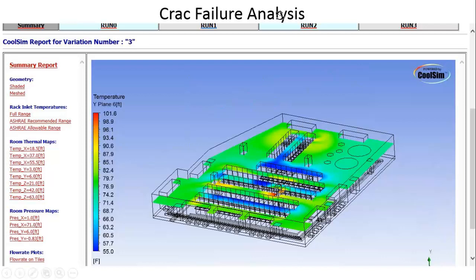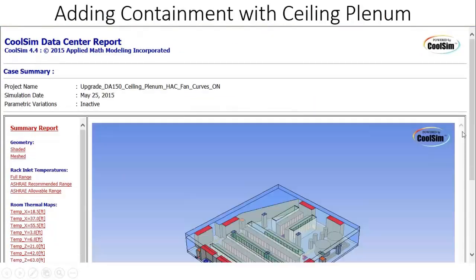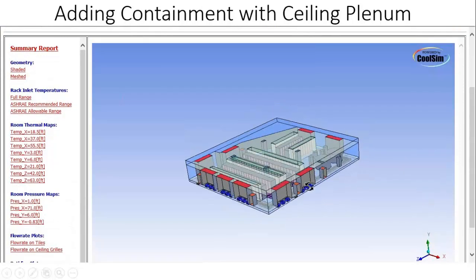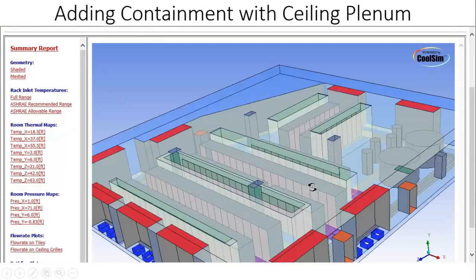Right, maybe not in this case, but that's definitely something that everyone should be looking at, and I'm sure everyone does. Just trying to get more bang out of the buck of your existing infrastructure before you start spending money. That's right. On implementing EC fans or replacing CRAC units or putting in containment. You do get some bang for the buck by just raising temps.